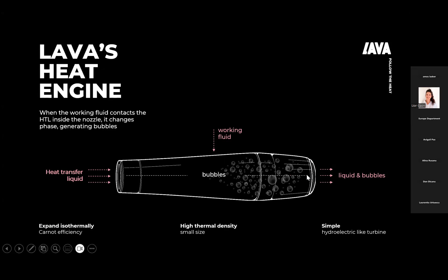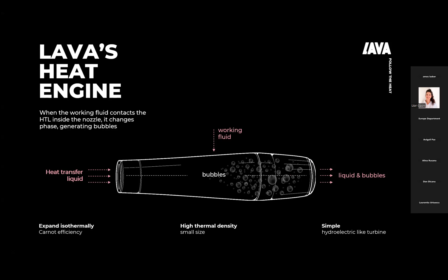At the end of the nozzle, we have a mix of expanded bubbles and liquid creating a jet. Just to understand: the bubble started as a 3% volumetric fraction, and they're emitted at 70%. It's creating a two-phase jet, almost isothermal expansion, where we proved in a proof of concept on an operating turbine that we can reach 95% isothermal expansion - 95% away from the red line that you see, into the blue line.